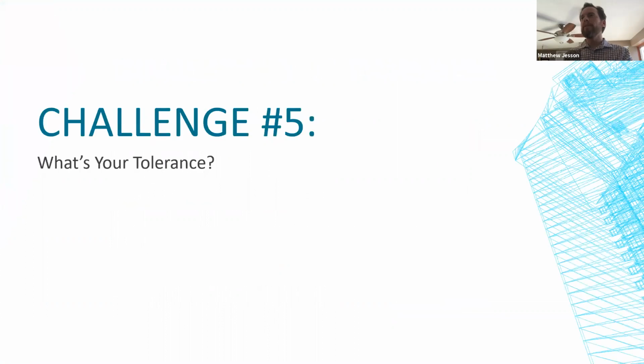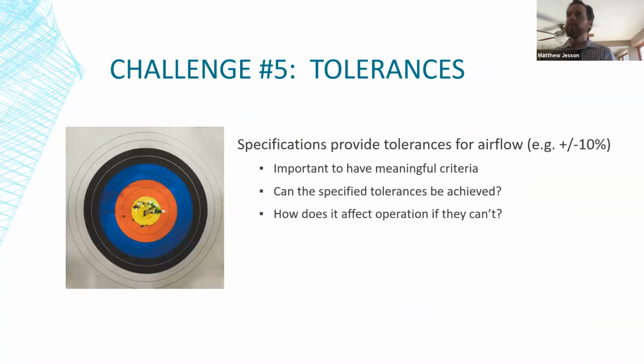But we were able to balance it in the end. So speaking of tolerance, let's get into specified tolerances here. What I'm talking about are, in the specifications for each job, the engineer will provide tolerances for the airflow in the balancing spec. And the classic example is plus or minus 10%. And it's important to have meaningful criteria. You have to have something to judge this by, some sort of target to hit.